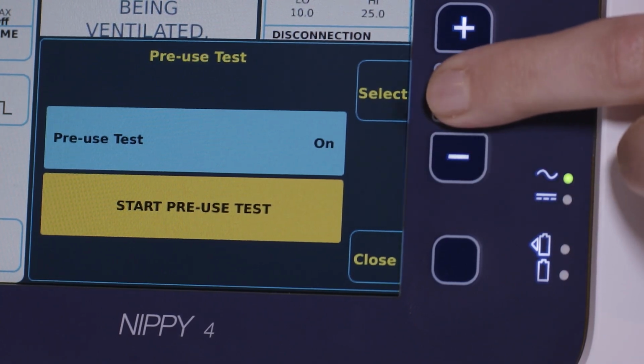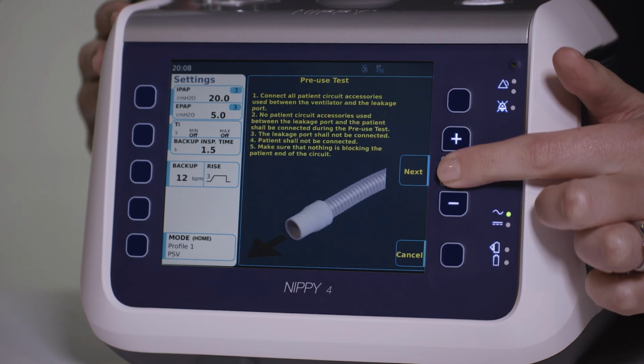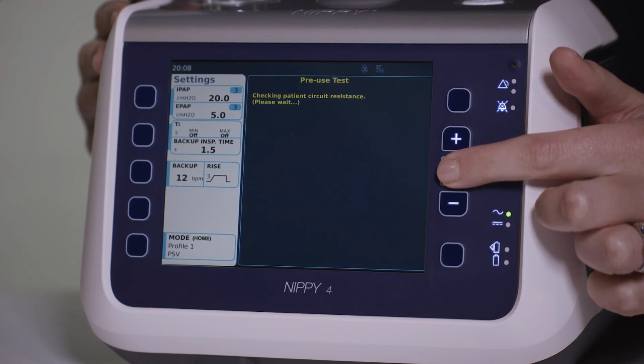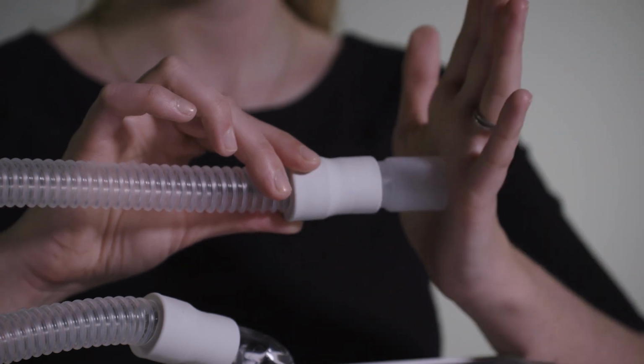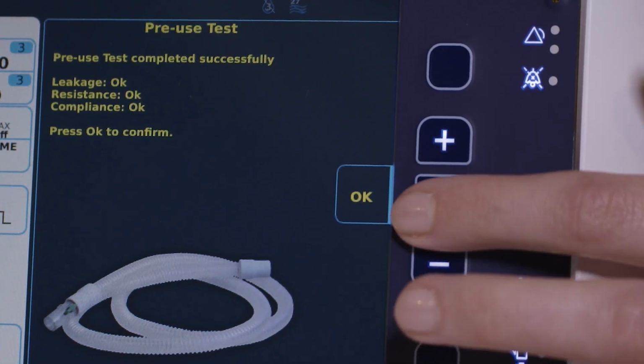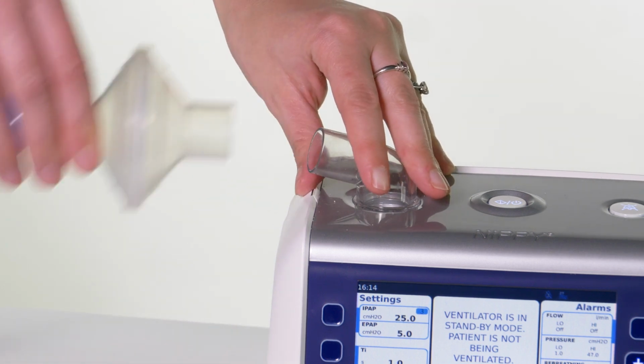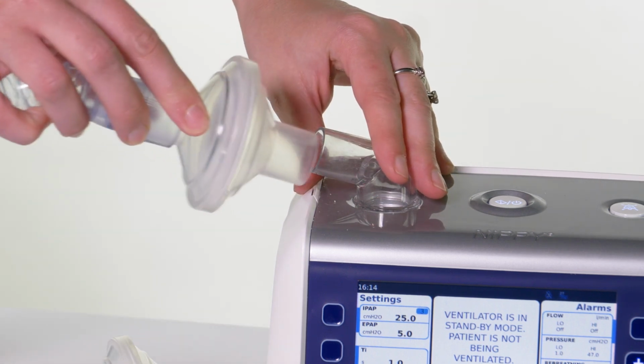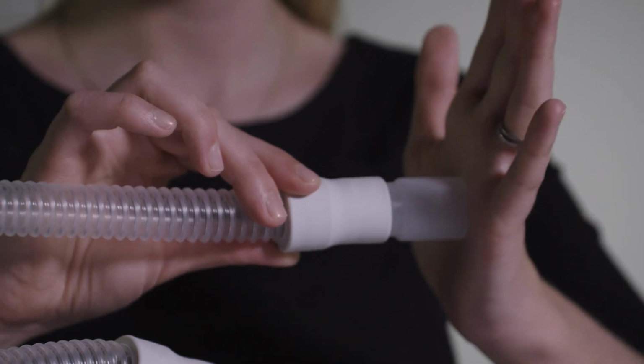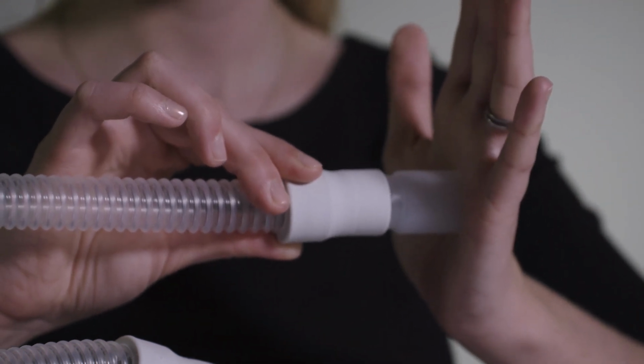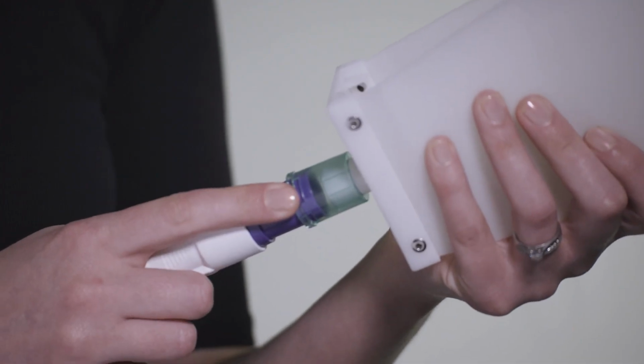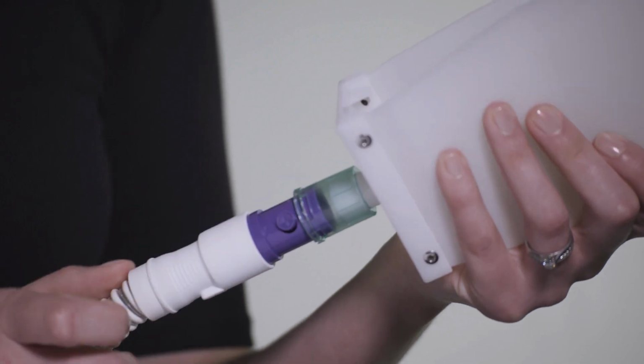It's important to note that breathing circuit configurations will all have slightly different resistance, compliance, and flow characteristics. This is why it is important that the Preuse test is carried out when a circuit or circuit component is changed, in order to optimize the delivery of patient's therapy. Whenever a circuit is changed, the alarms on the ventilator should be actively tested by creating a disconnection and circuit blockage, and also by testing the rebreathing alarm by temporarily occluding the leak port for 3 consecutive breaths.